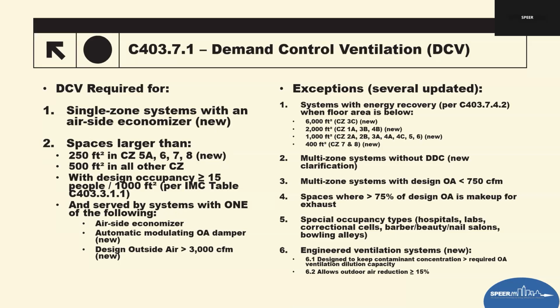Field inspections: verify that CO2 sensors are installed and located correctly. Confirm the outdoor air damper modulates with occupancy. Trend logs or the BAS data basically should show reduced outdoor air at lower occupancy count. And then check that the DCV sequences do not conflict with minimal ventilation rates. I know that was a long one.